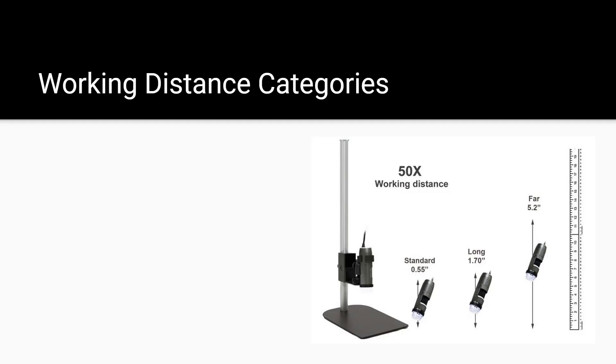Our microscopes come in three main working distance categories, which are standard, long, and far. Most of the models in these categories can focus to infinity, which means you can put them as far away from your subject as necessary in order to have enough room to use tools or move the subject around. The difference between them is how much magnification you can achieve at a distance. So, standard working distance models have a magnification range of 1 to 230 times, and at 50 times magnification, you will have a working distance of approximately half an inch.